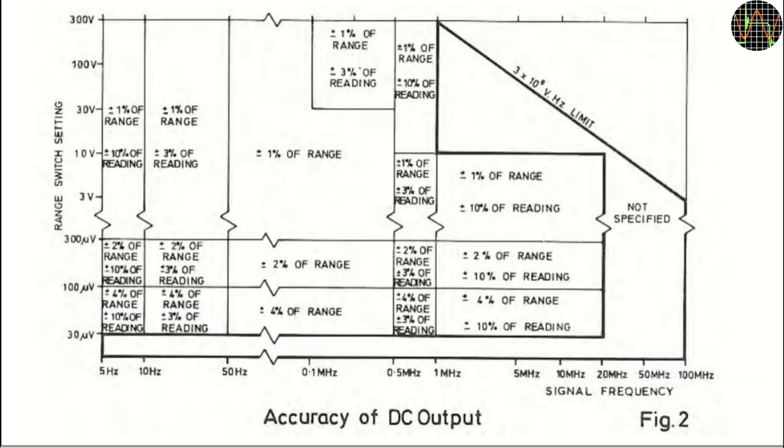Because the real thing looks like this table in the 9300 manual. The slope on the right indicates that you are not allowed to put in very high voltages with very high frequencies. This is simply because the impedance of capacitors drops with increasing frequency, and at high voltages some significant currents would start to flow.